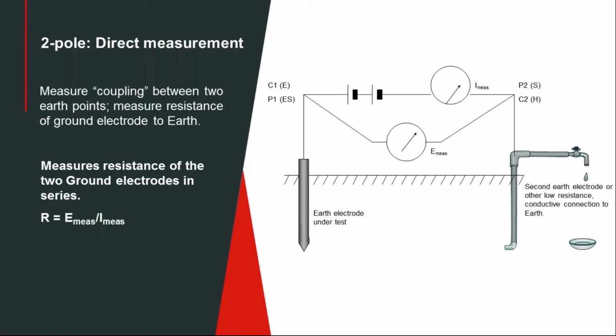Okay, so we'll start with looking at the simplest way to do this, and this is the dead earth or 2-pole method. This is using a ground tester very similar to the way you would use a DMM, which is to say you take 2 leads and you hook them from here to there and you make the measurement in between. So essentially that's what you're doing. You're reducing the tester to a 2-pole configuration. You can do that by shunting them together. In the old days, you shunted the poles together. The newer testers have selector switch positions for every combination.